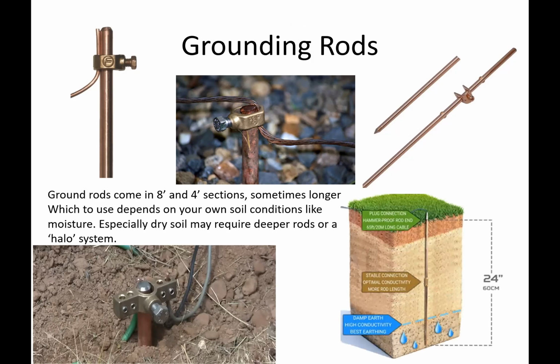What system do you have to use? I've also got up on the screen a little cross section of a theoretical backyard section of earth, approximately 24 inches deep. Now, I don't know of any rods I've ever come across that are only 2 feet deep — most of the rods I come across are 8-foot sections. But I suppose if you find you only need 24 inches of rod to get to damp or highly conductive earth, then that's all you need.